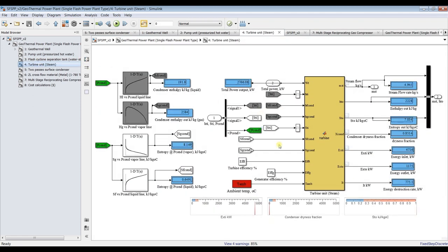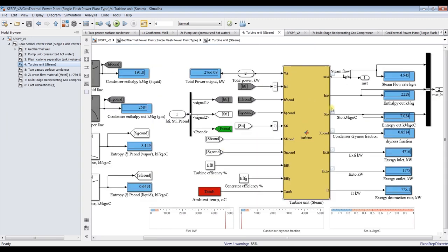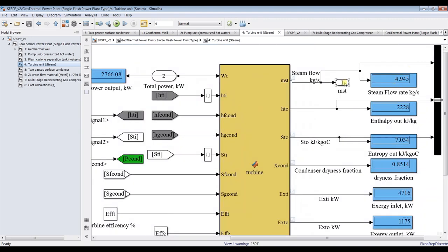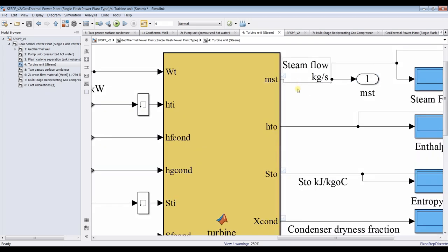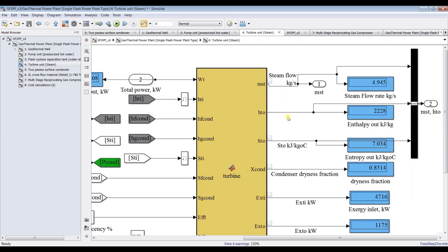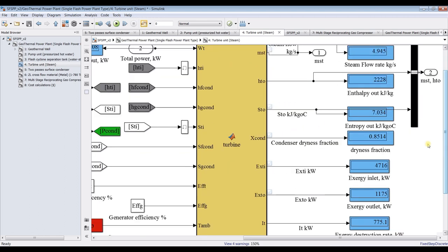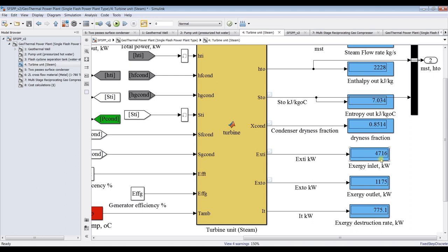For the turbine unit, we need to calculate steam mass flow rate. What is the steam mass flow rate needed? In this case, it is 4.9 kg/s to generate the required power. We also get outlet enthalpy, outlet entropy, dryness fraction at exit, exergy from the turbine going toward the condenser, and exergy destruction rate.